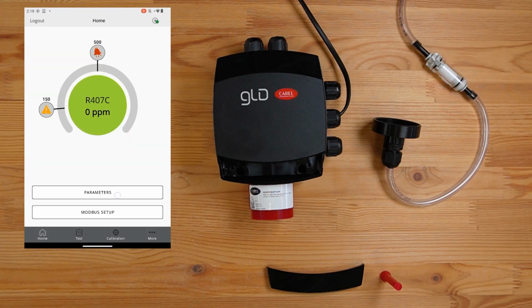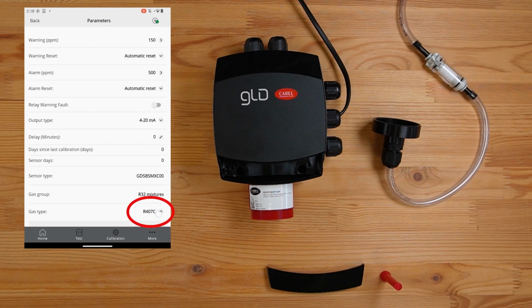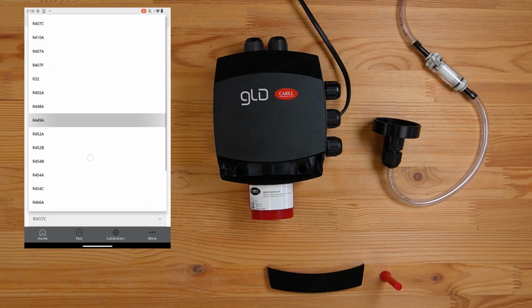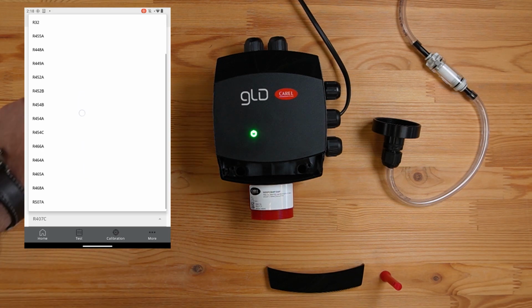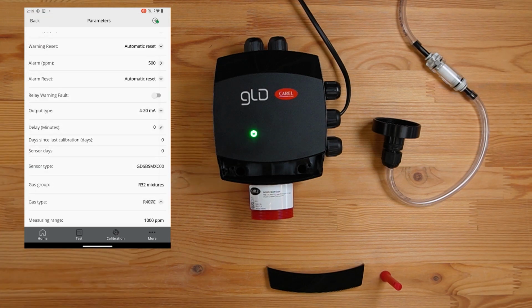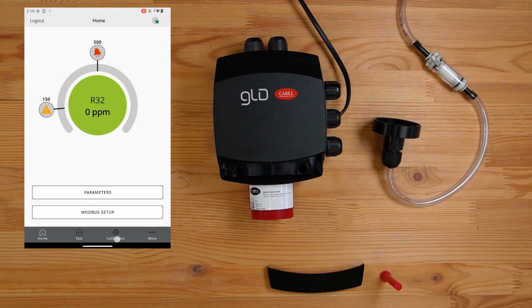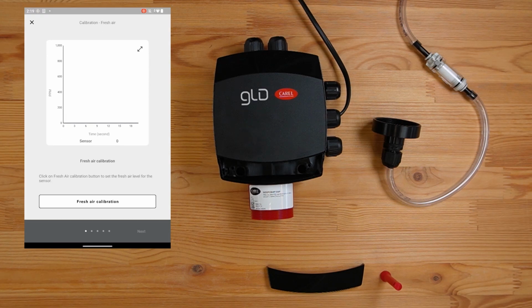Start by changing the unit to the gas type you are using to calibrate the sensor. Go to Parameter. Scroll down to Gas Type. Select the chosen gas type. Click Back. Now choose Calibration from the footer menu in the app. Before connecting the calibration kit, make sure the sensor is ready and free of gas or other sources of pollution.